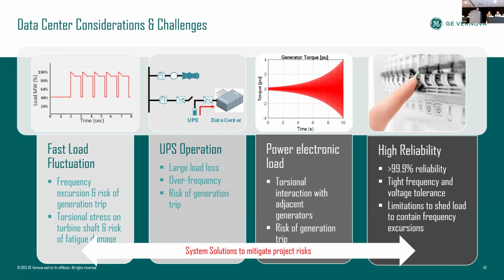From the power generation point of view, this pulsation will act like a big, large step when the profile first starts, right? So our generation systems would need to be able to absorb that pulse through various means. The conventional generation cannot absorb the pulse, so we need some energy storage or some kind of means to help facilitate the transition so that large step can be absorbed by the system. And this pulsation also has an impact on the torsional aspect of the shaft, particularly if it has a frequency content which coincides with the torsional frequency. And that is a significant risk, and I think this has been discussed previously, that such considerations are an important part.